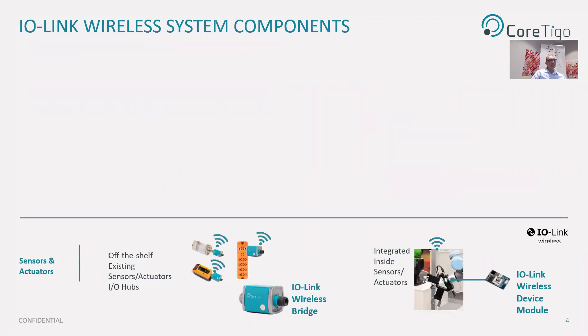So let's first understand what are the components of an IO-Link Wireless solution. At the device level, there are two options for creating IO-Link Wireless devices. The first is to connect an IO-Link Wireless bridge to off-the-shelf devices. These can be either IO-Link or digital devices, and the bridge can be connected to sensors, to actuators, and even to IO hubs, thus enabling multiple IO devices to transmit wirelessly through a single bridge.